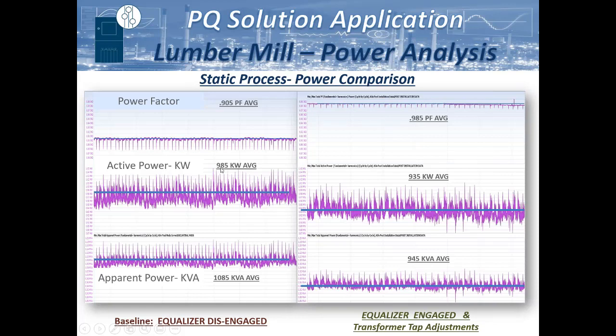But you can look at the kW with the average of 985 versus 935 once it was treated, as well as the kVA. So we can have a significant impact on kVA reduction. This is particularly important in a lot of instances now where we have perhaps some production capabilities that are overseas, where it's harder logistically to get it over here. We have several plants that are trying to add a lot more production lines to existing facilities to make up for that demand. And sometimes the utility just doesn't have any more capacity, or the utility has capacity, but the facility doesn't, so they'd have to add a whole new transformer.